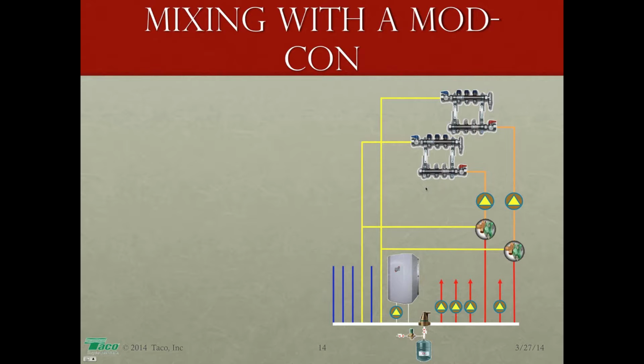A lot of folks, we see this happening a lot. Because it's a low temperature boiler, we see an awful lot of system designs out there that are designed around one water temperature. I have one water temperature for everything. The boiler can go low. It makes it very simple. And I like simple. But sometimes we don't want to go so simple that it becomes simplistic. There's a difference between simple and simplistic.